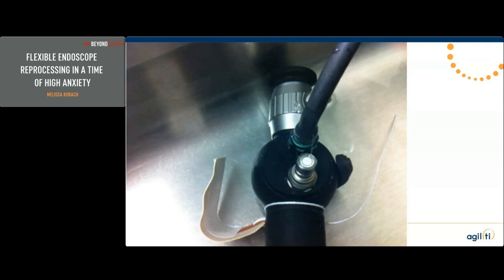But if you look at that light guide prong, right on the edge you'll see almost what looks like a little string hanging out of it—a little bitty string of champagne-like bubbles coming out of that light guide. This endoscope had been bonked on a counter, and that light guide hit the counter, and that's all it showed.